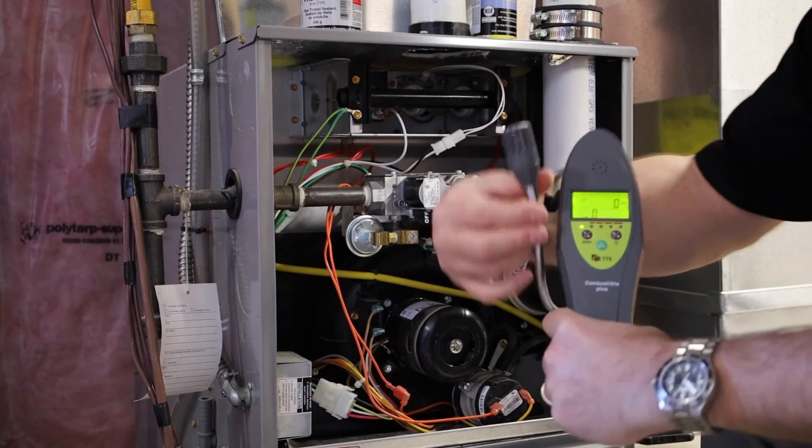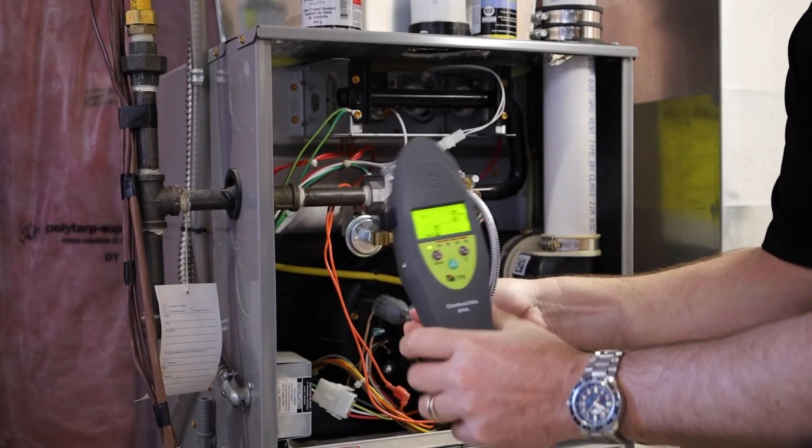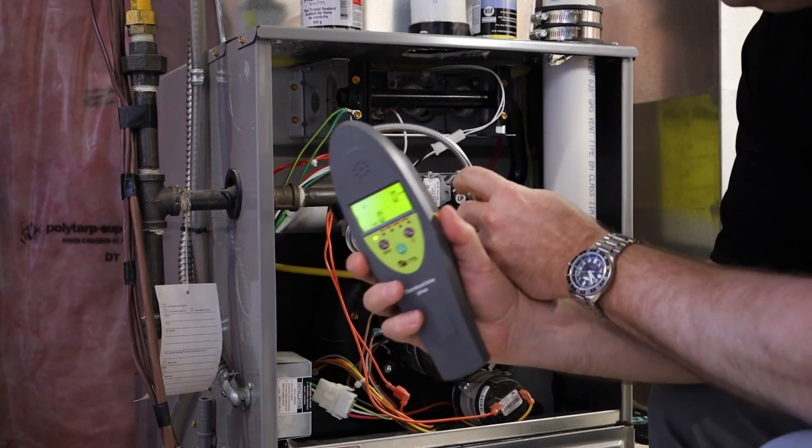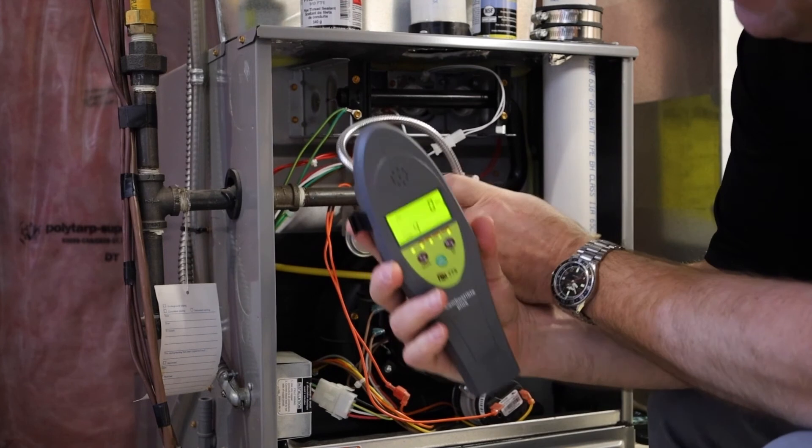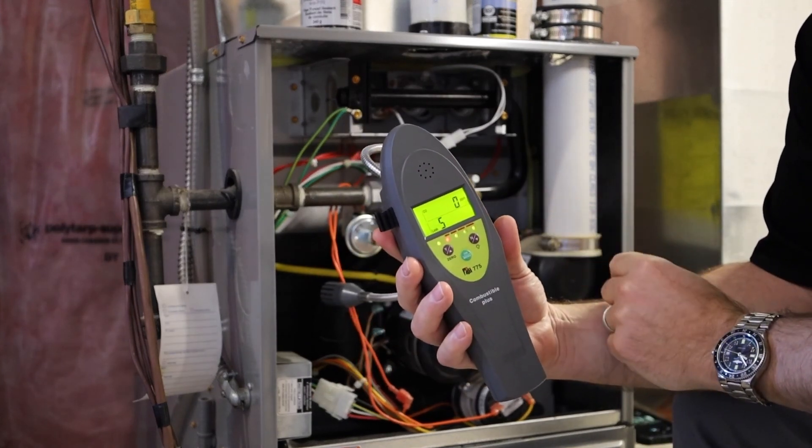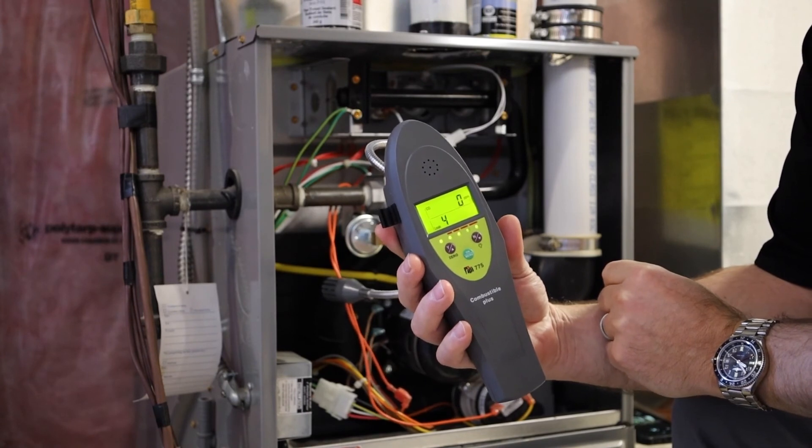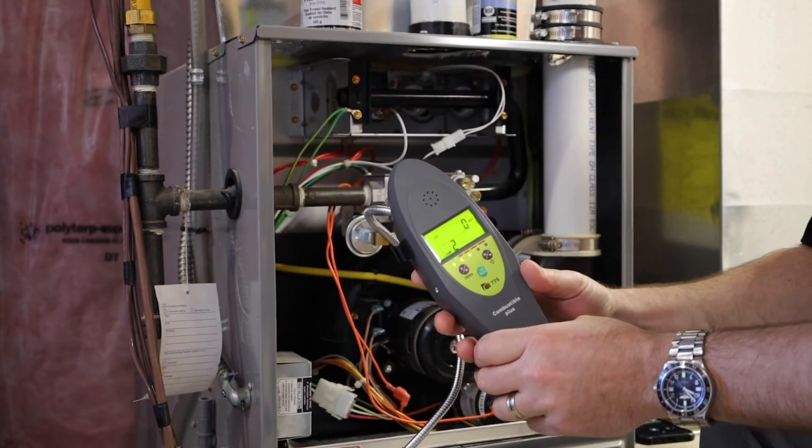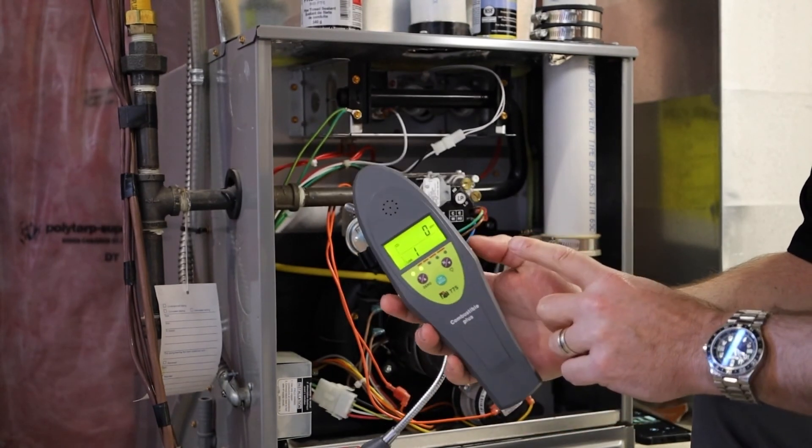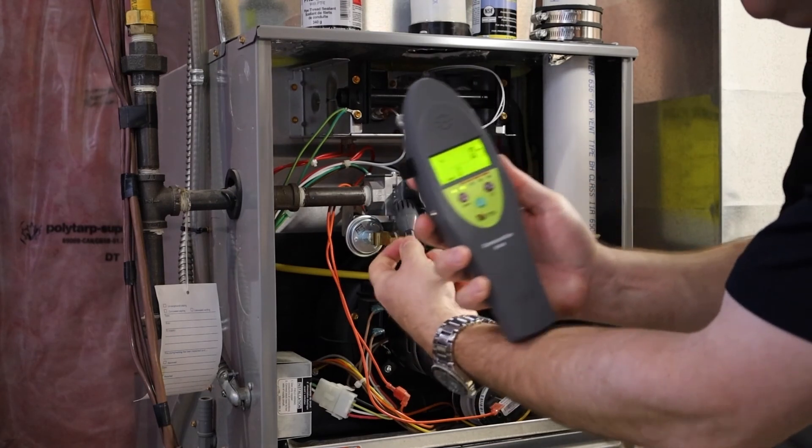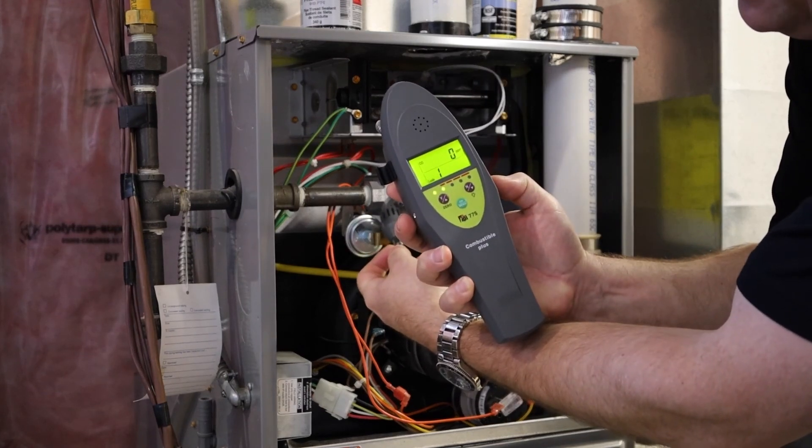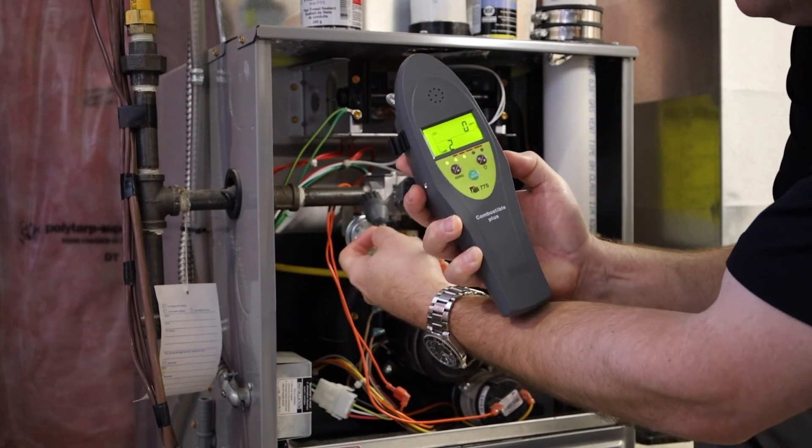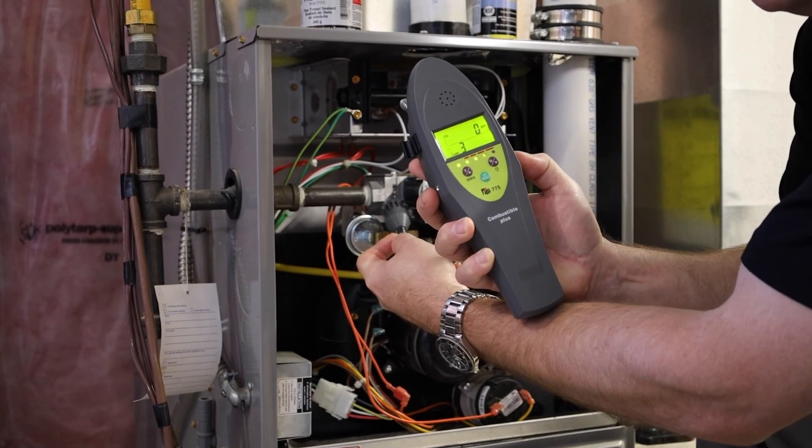So again, gooseneck. I'm going to go over to my leak. I've got my thumb wheel on the side. So I'm going to just go over to my leak here. And of course, there it is, going off. Oh, that's a big leak. So I'm at five. So that indicates that leak is between 2,000 and 2,500 parts per million. And again, if you want to look around for the leak there, you got it there. And then you have the tune button on the side. So you can actually tune it out. And of course, when it goes to higher ppm, it's going to start beeping again.